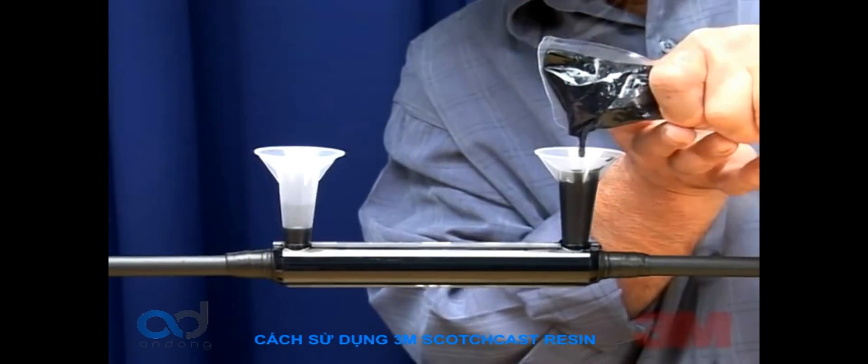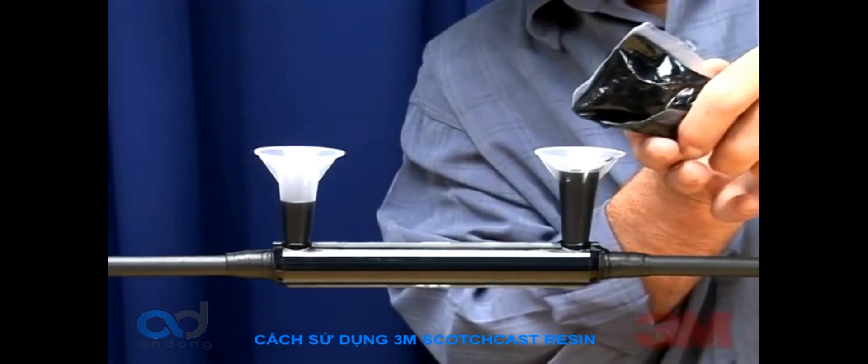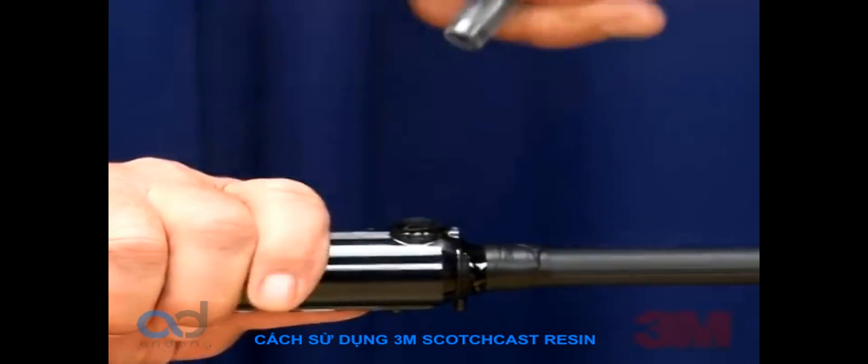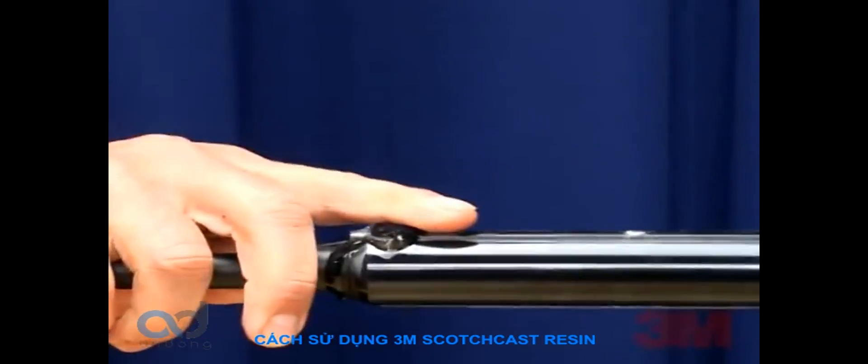Splice cure time is 1.5 hours and is submersible in 4 hours. Clip off the spouts if desired. Your 82-A1 power cable splice is now complete.